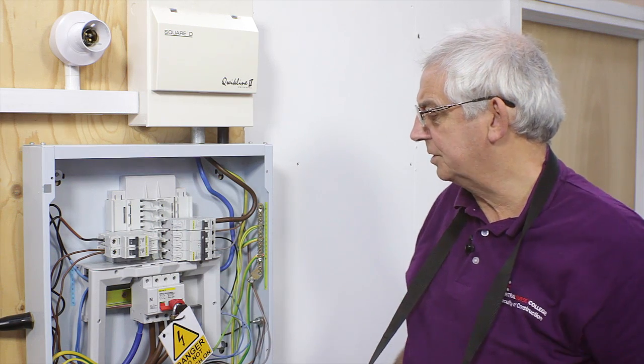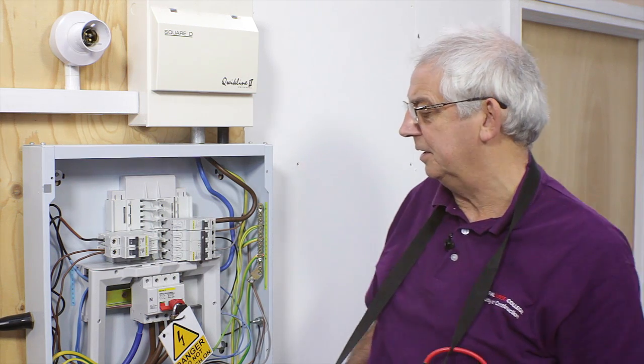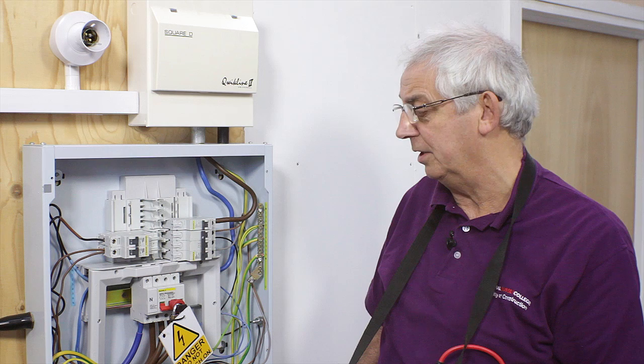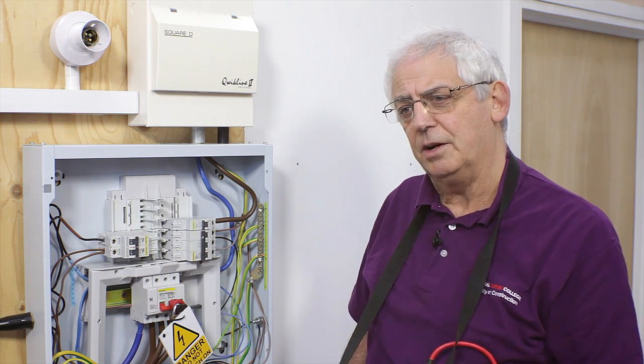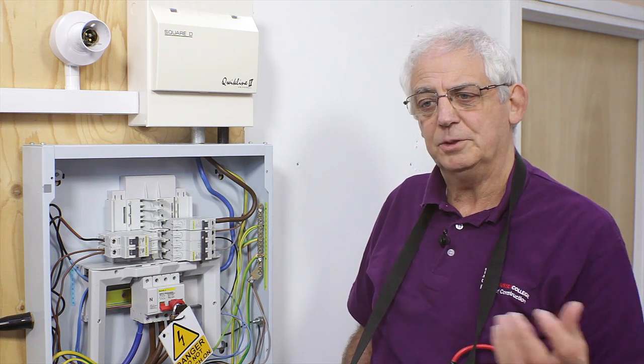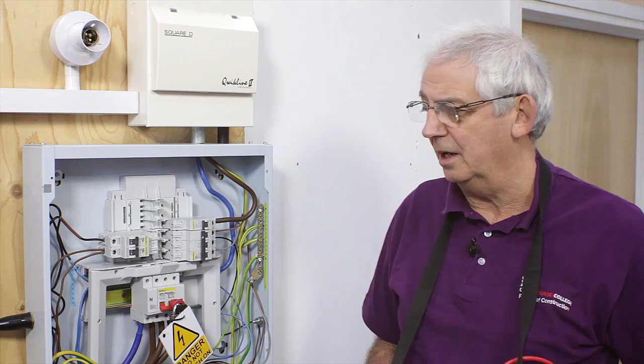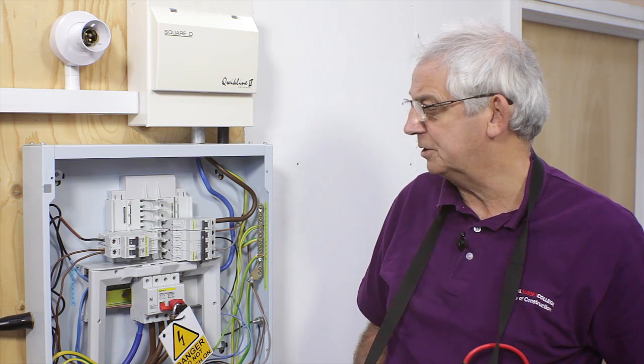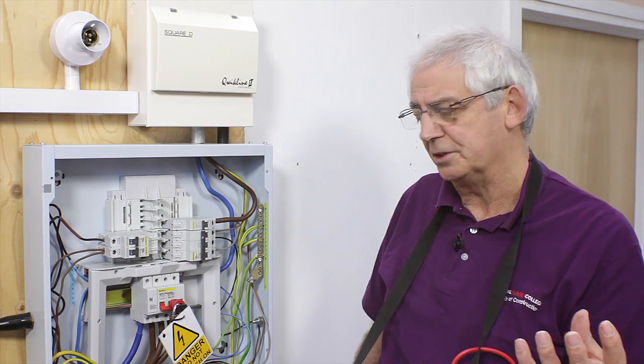And of course, while I was carrying out those tests, particularly the test between live conductors or line conductors and neutral, I should go around and operate any switches which may be controlling lights and devices, just to make sure that I'm testing the whole of the circuit.